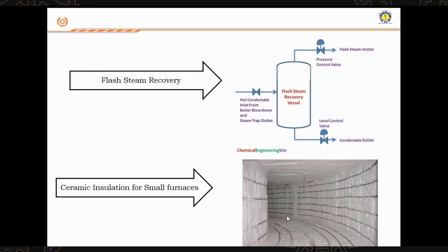Normally you give blow down, and there is the steam trap outlet. You give the blow down because of the TDS that is present, the total dissolved solids. So this is one of the finest technologies we have seen: the hot condensate coming can go into a flash steam chamber or vessel, where it flashes and you get low pressure steam, and the condensate is recovered. That low pressure steam can be used again in the boiler. So that is one advantage of flash steam recovery, and your condensate recovery is also very good.